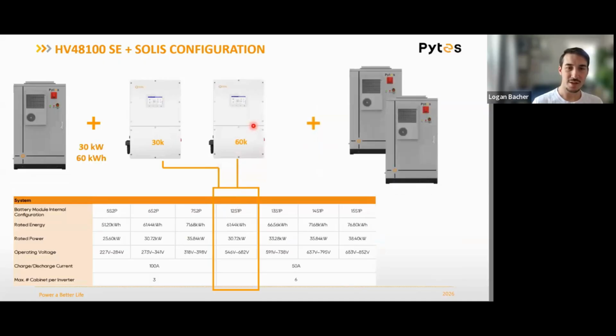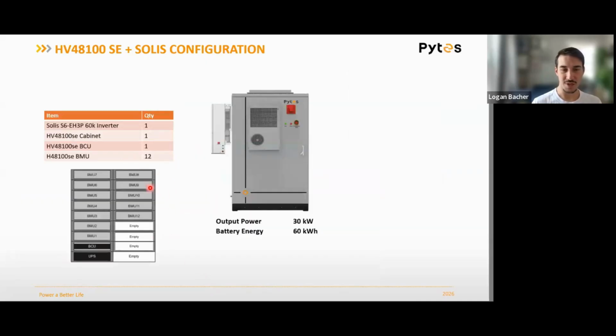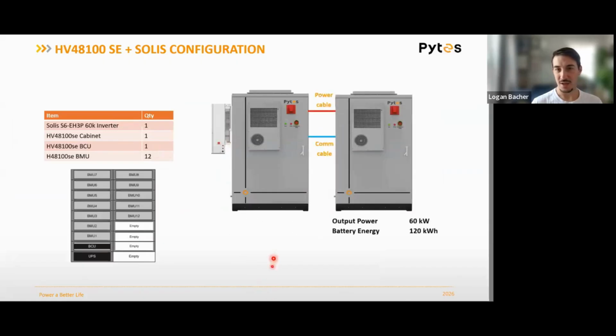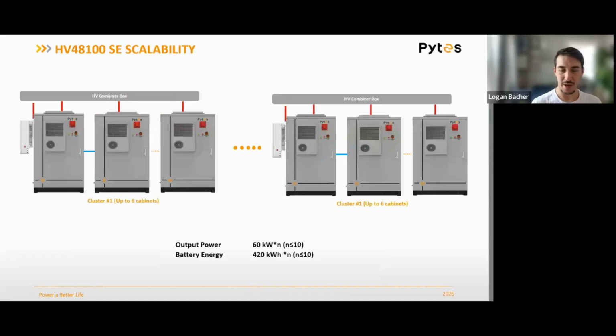All those concepts apply to Solis too, but actually I almost think the Solis designs can be a little simpler because, again, all of their inverters, 30K, 40, 50, 60K across the board, they all have this higher input voltage of 800, which means we can do 12 batteries in series for any of their models, and actually we can go as high as 14. So, kind of another example there with Solis, very simple BOM, inverter can mount right on the side of the cabinet. And if you need more than what one cabinet can produce, you just have to add a second cabinet, and then that basically doubles your power output.